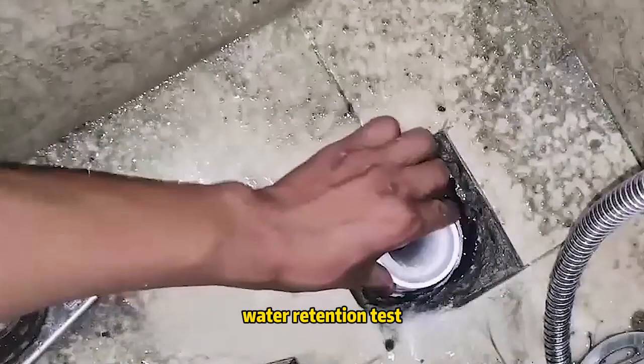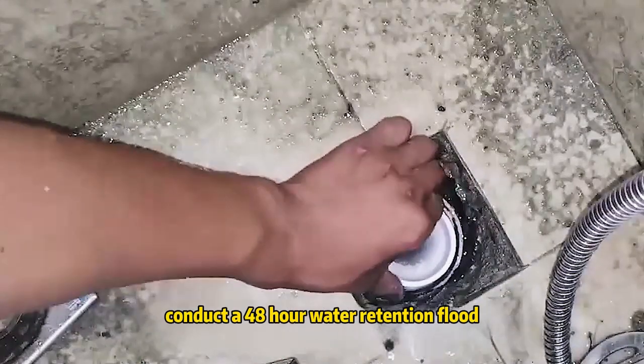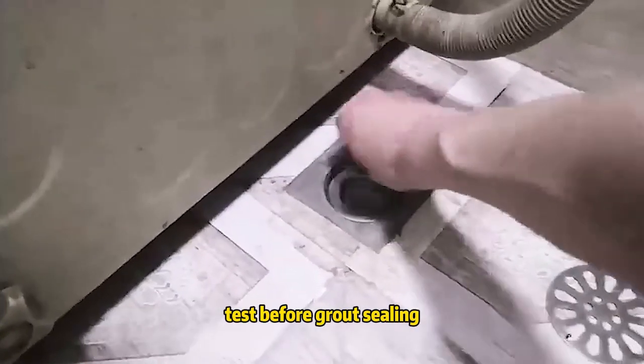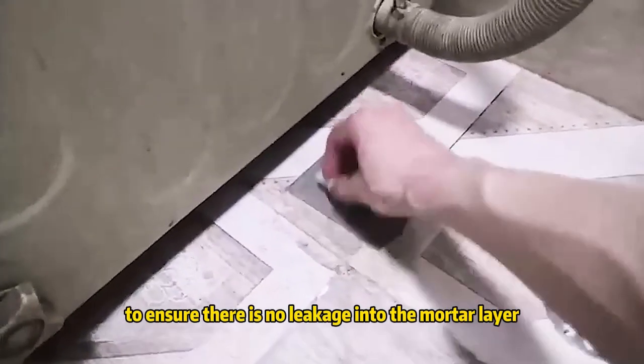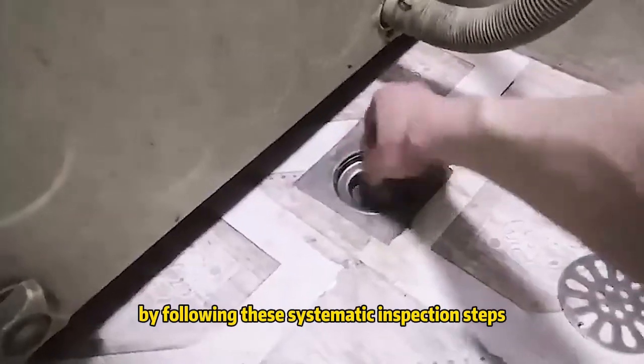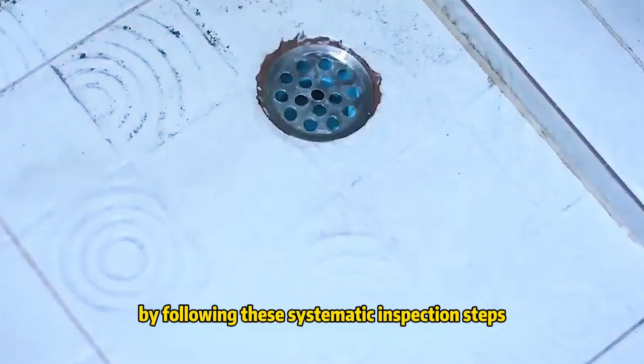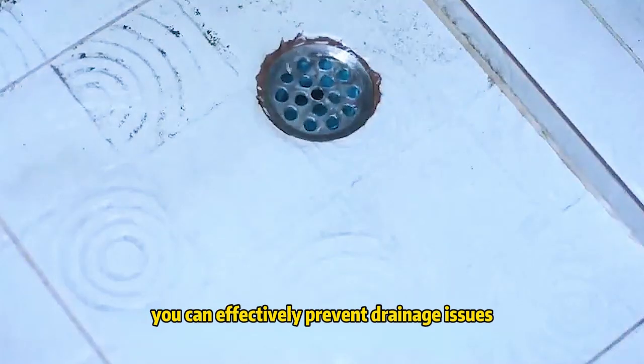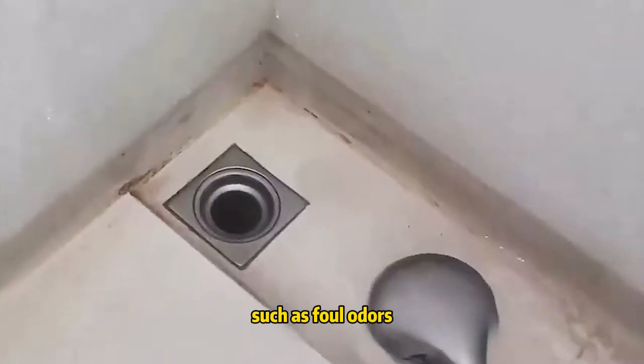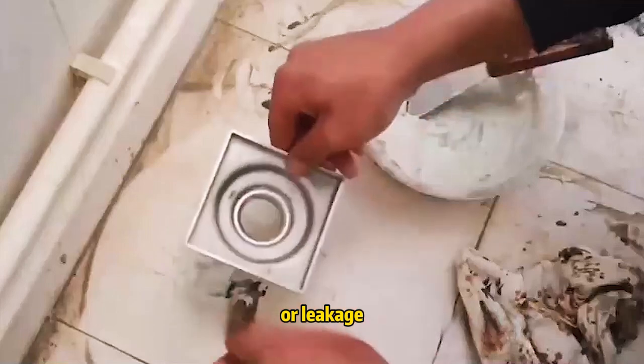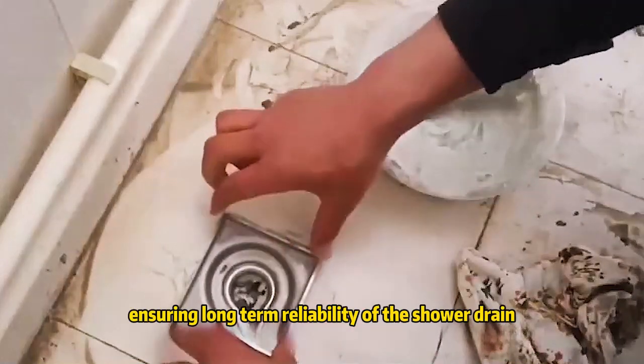Water retention test. Conduct a 48-hour water retention flood test before grout sealing to ensure there is no leakage into the mortar layer. By following these systematic inspection steps, you can effectively prevent drainage issues such as foul odors, standing water, or leakage, ensuring long-term reliability of the shower drain.